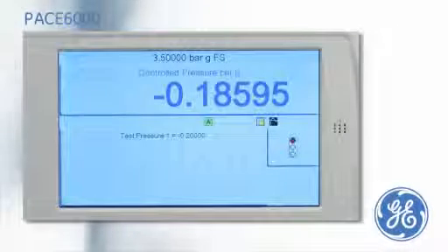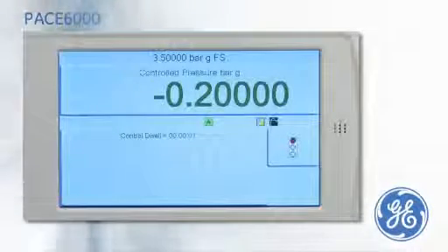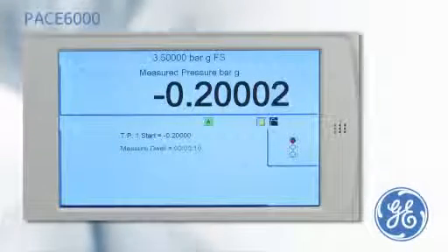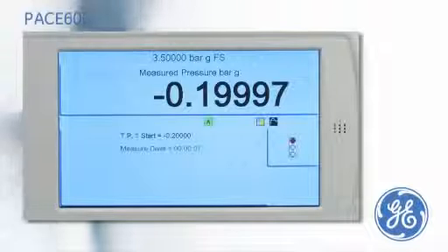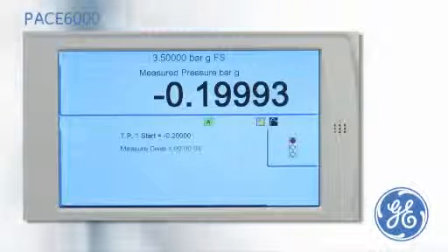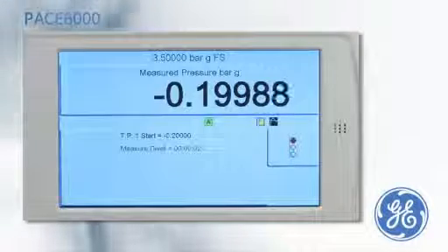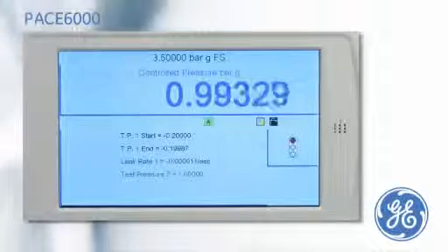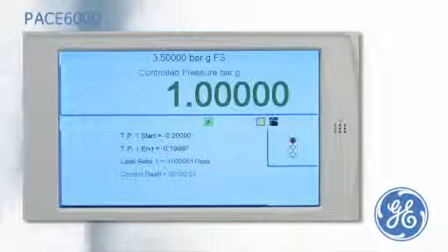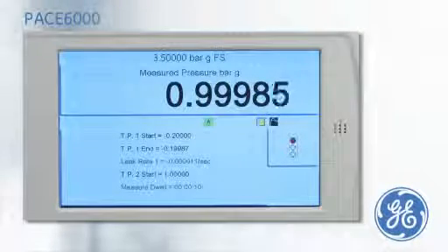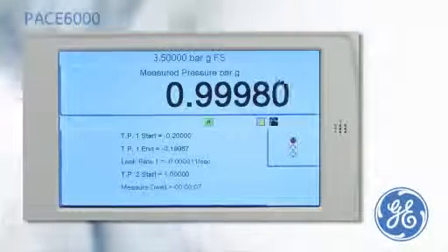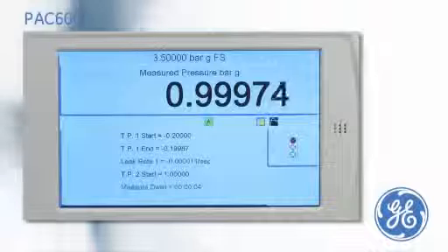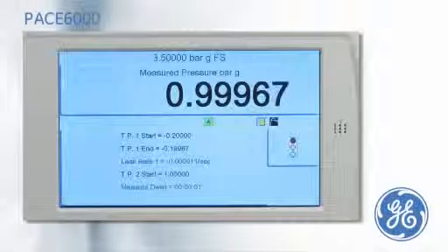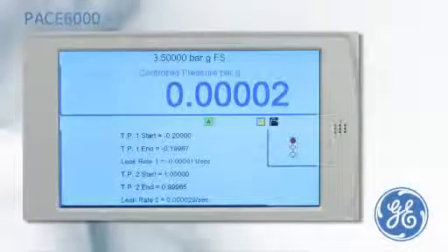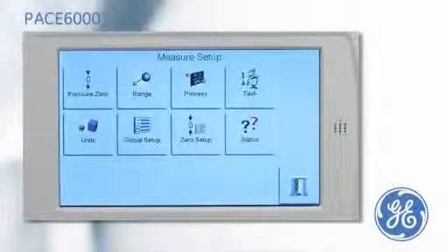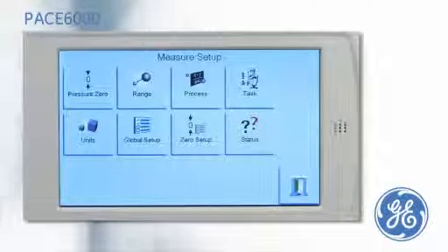Once the test has been started, the PACE will evacuate the system to test pressure 1. The PACE will measure any pressure change during the leak test period, called measure dwell. The leak rate is calculated and displayed. The PACE now repeats the leak test with a positive test pressure 2 before a final display shows the start-end pressures along with the leak rate of both tests. For the calibration of pressure switches, the PACE has an optional dedicated switch test task.